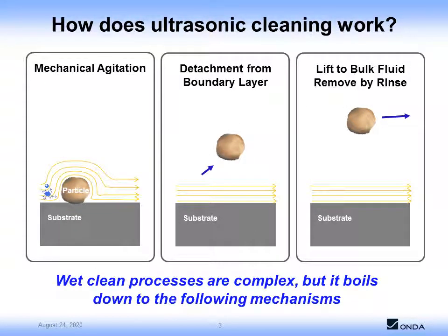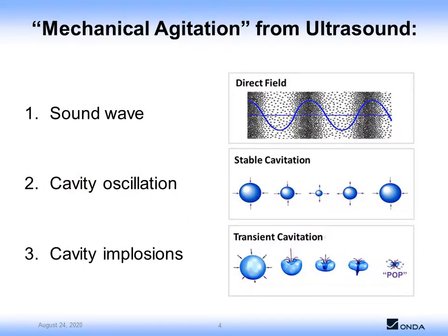Let's begin by reviewing how ultrasonic cleaning works. It starts with some form of mechanical agitation that disrupts the hydrodynamic boundary layer, allowing the particle to be detached and lifted into the bulk fluid. Of course, this mechanical agitation here is in the form of ultrasound. A sound wave generated by a transducer propagates and oscillates between the positive and negative pressure at the drive frequency. When there is a rapid change in pressure in a solution with gas, acoustic cavities form. With less gas, there are fewer acoustic cavities that are generated.